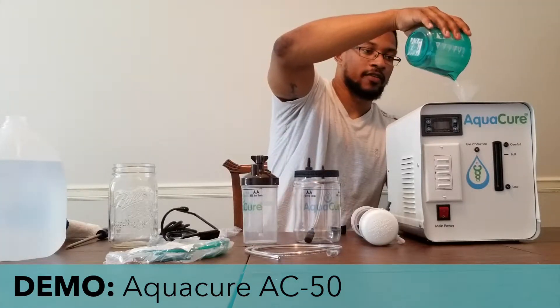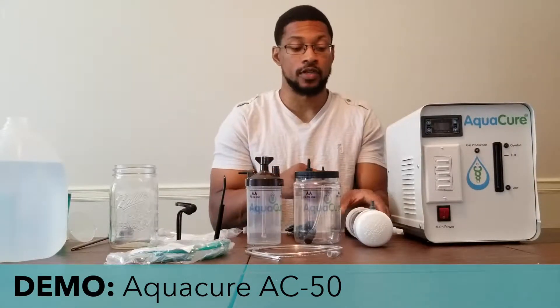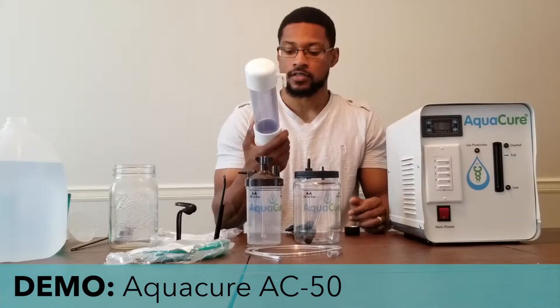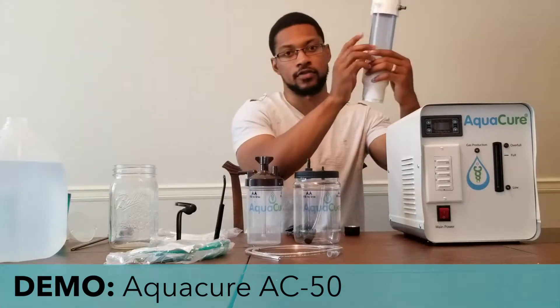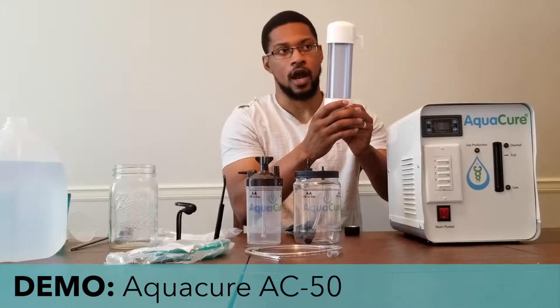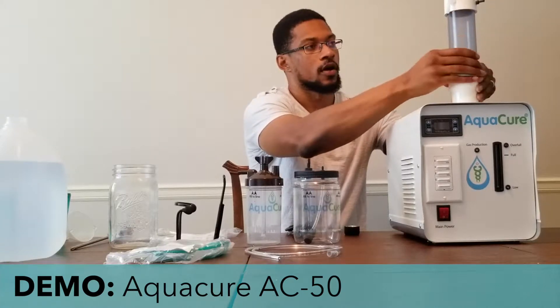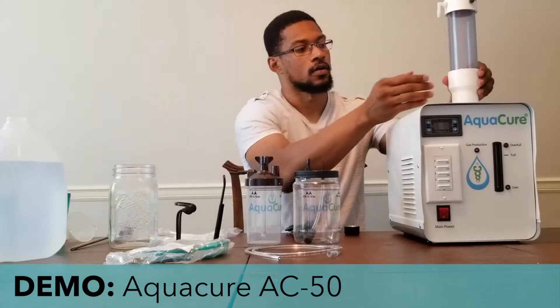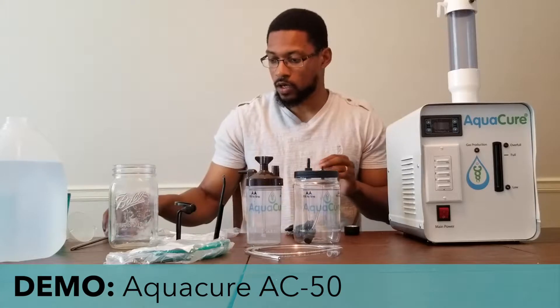When you're doing this, the unit will fill up to about 70 to 80 percent full, and that's where the manufacturer recommends it to be. The next step is to put on the tower cap, which screws on top. This is another filtration mechanism to help filter out the oxyhydrogen from the lye mist that could be generated with the unit.